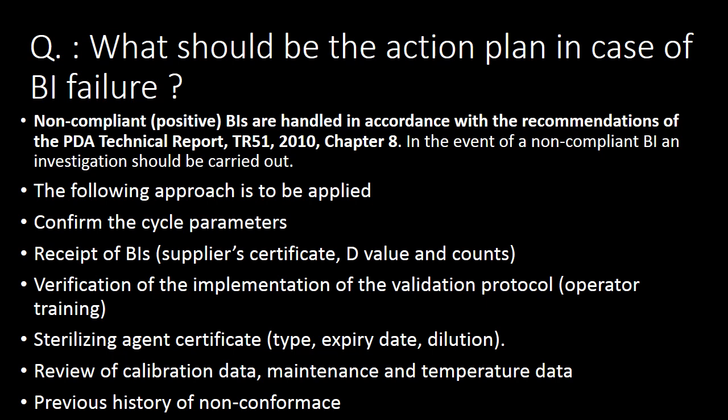During the investigation of non-compliant or positive BIs, the following approach shall be applied: confirm the cycle parameters; verify receipt of BIs and implementation of the validation protocol; check sterilization agent certification; review calibration data, maintenance, and temperature data; and verify previous history of non-conformances.